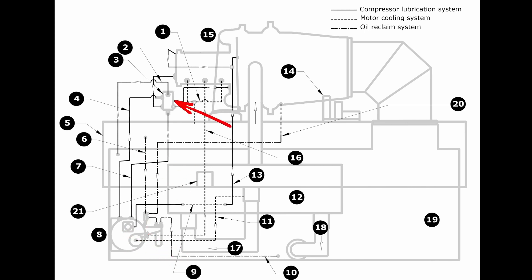As the oil will separate in our separator, it drains out a bottom port and returns to our oil tank housing. That is the only function that the oil is trying to do in this system. It is flowing through the cooler, going up to our tube bearings, draining back down through our separator, and then coming back to our tank.